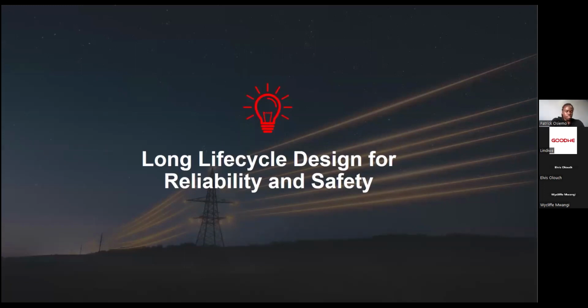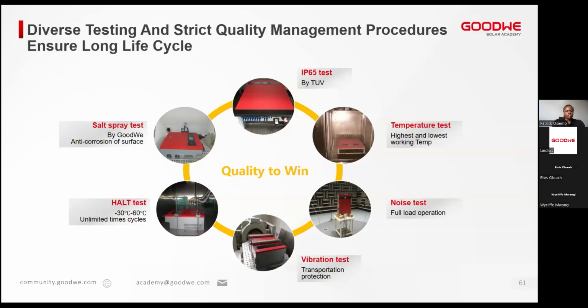One more typical application is if you want your installation to be a long-lasting solution, then GoodWe is a viable option for you. Our designs offer a long life cycle and are reliable and safe. Why or how do we say it is reliable and safe? The inverters are scrutinized and taken through very intense tests. We have an IP65 test, which is done by a third party. We have a temperature test, noise test, vibration test, salt spray test, all these tests just to ensure that the inverter is exposed to harsh environments, but still maintains its long life cycle or shelf life and generates power as required or as stated in the data sheets and manuals.